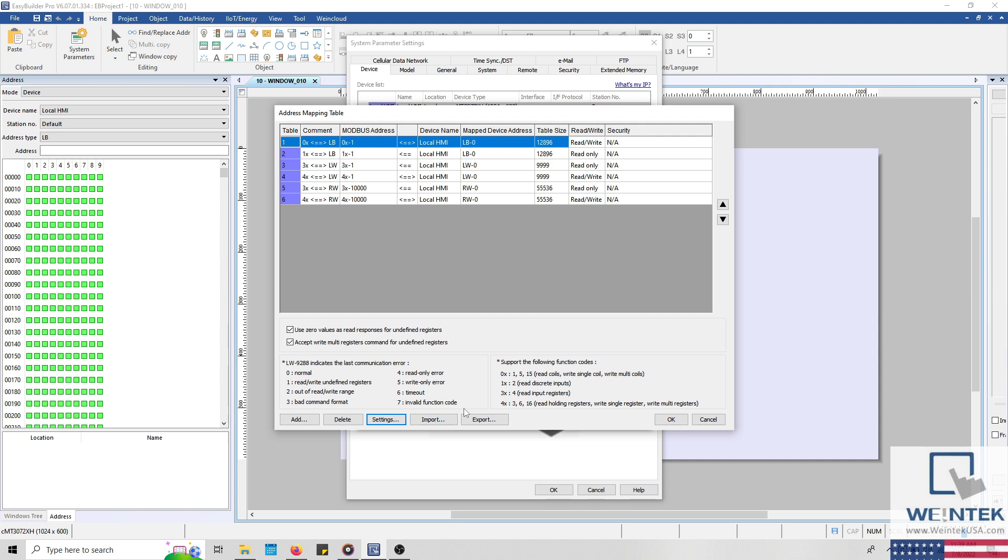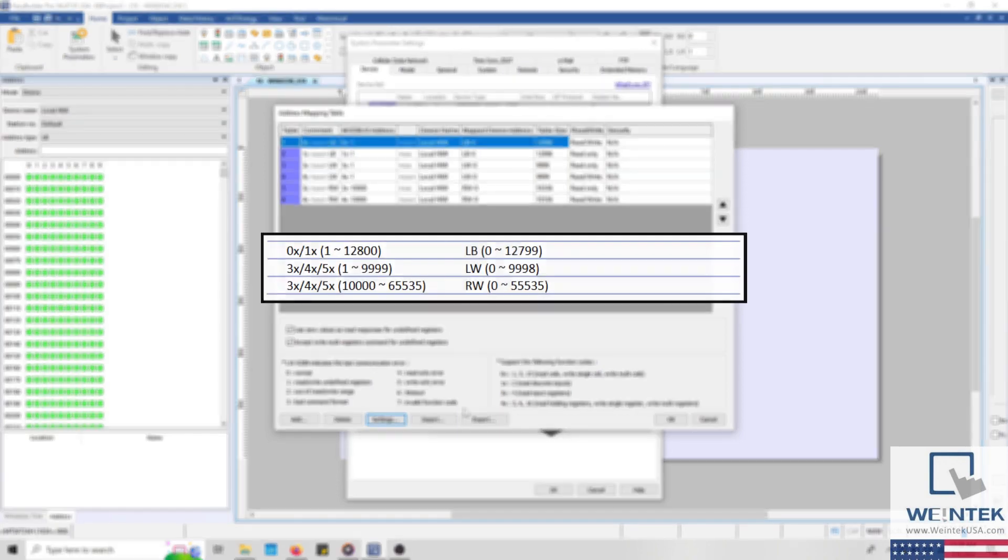The Modbus gateway is an extremely useful feature, but I would like to note that although an HMI can function as both a Modbus TCP server and a Modbus RTU slave, only one Modbus server driver can be configured as a Modbus gateway. The Modbus mapping defined within the gateway will only applied to the specified driver. Other instances of the Modbus server driver will utilize the default configuration shown within the following diagram.